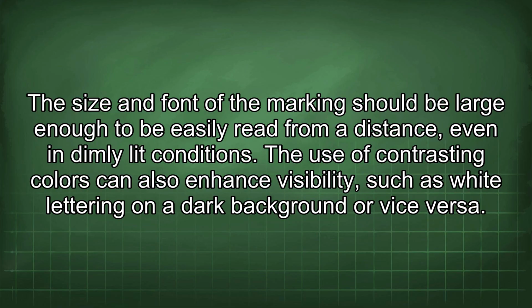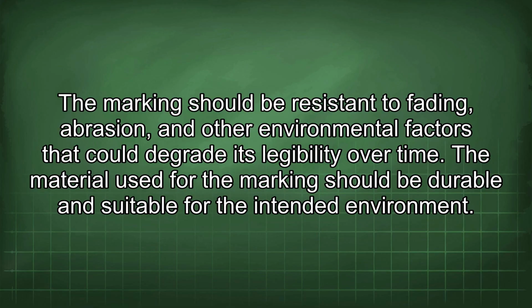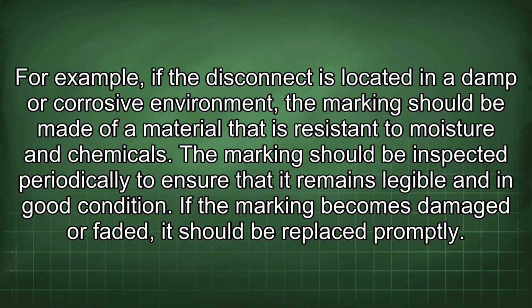The use of contrasting colors can also enhance visibility, such as white lettering on a dark background or vice versa. The marking should be resistant to fading, abrasion, and other environmental factors that could degrade its legibility over time. The material used for the marking should be durable and suitable for the intended environment. For example, if the disconnect is located in a damp or corrosive environment, the marking should be made of a material that is resistant to moisture and chemicals.